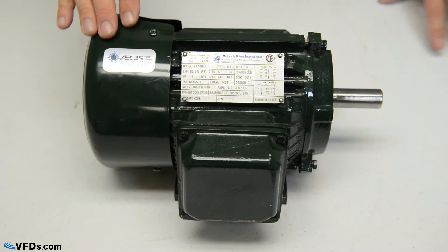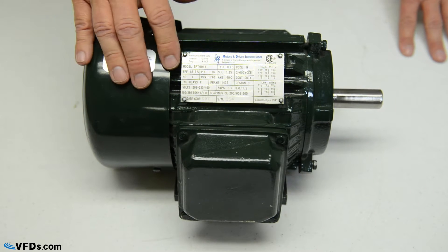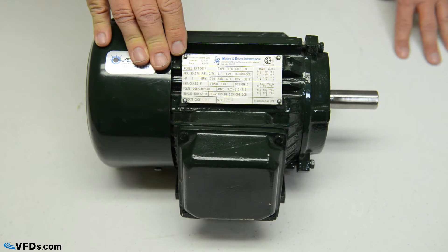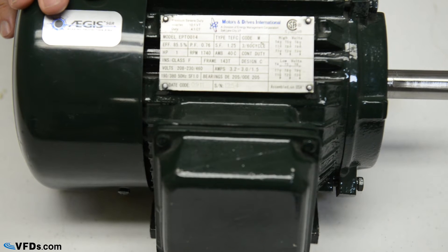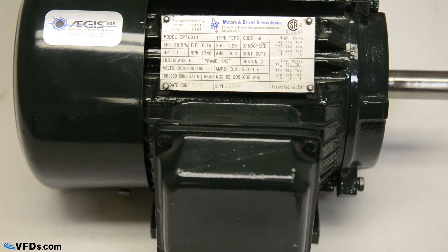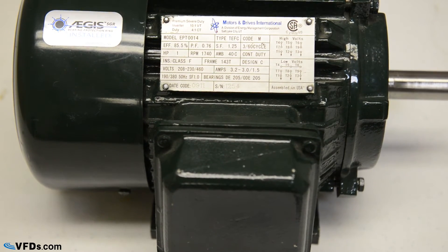We have here a very high quality motor made specifically for variable frequency drives. It's a Motors & Drives International motor, and it's one horsepower. This motor has a stainless steel nameplate. Arguably, the nameplate is the most important part of the motor — it gives you the voltage, the speed, the amps. It also gives you the service factor, which tells you how much you can overload that motor. This is a 1.25 service factor motor, meaning you could actually overload it 25%. We recommend at least a 1.15 service factor motor for any motor used with a variable frequency drive.